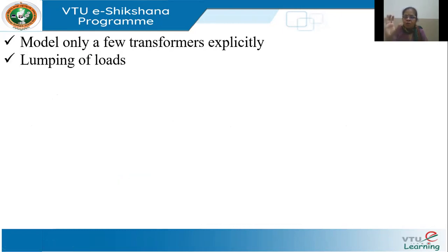And only a few transformers we model explicitly, with the connections. It may not be necessary at all places. Otherwise, I can simply model the transformer as an R-X, simple, like a line. But where it is necessary, for the three-phase transformers, I have to take into account the modeling of the connections, and lumping of the loads. I can't represent each load individually. If I have an industry, I can't go on modeling all of them. Or in a feeder, if four industries are connected, it may reduce the modeling complexity to lump all these four industries and model them as one unit. If I have 1,000 houses connected, I can just take it as a lumped load and model it with some characteristic. That is called lumping.